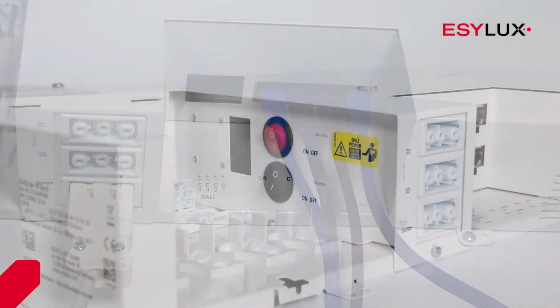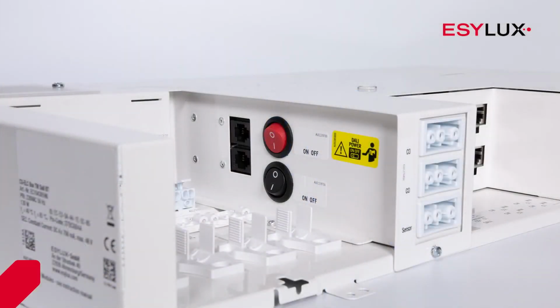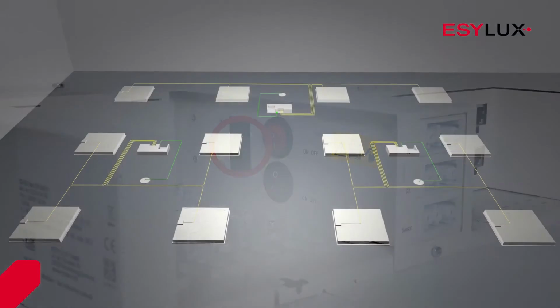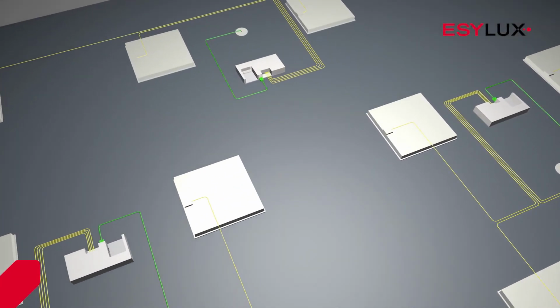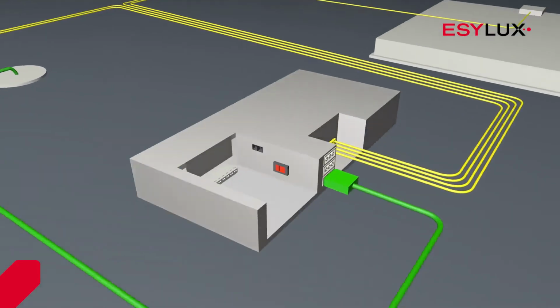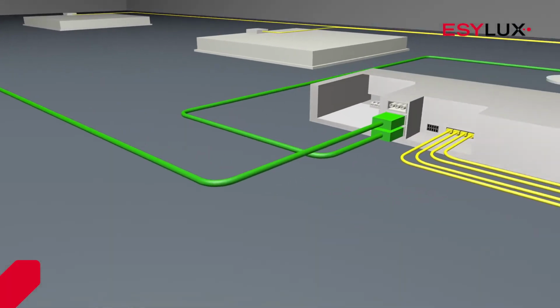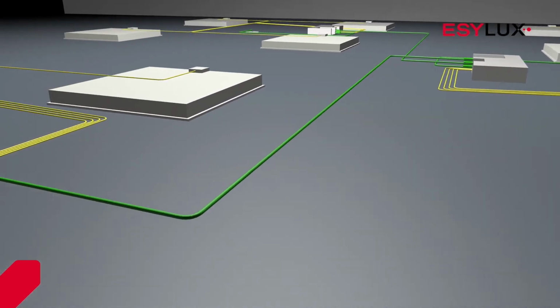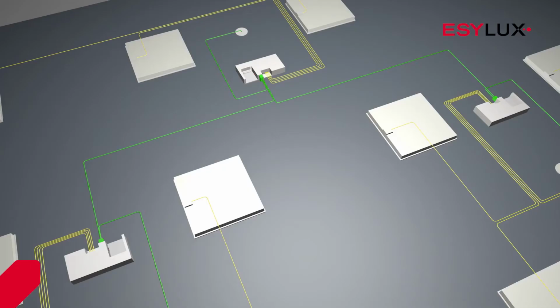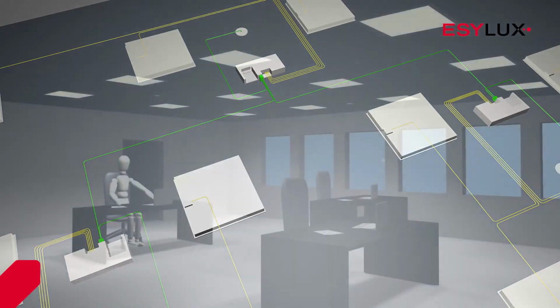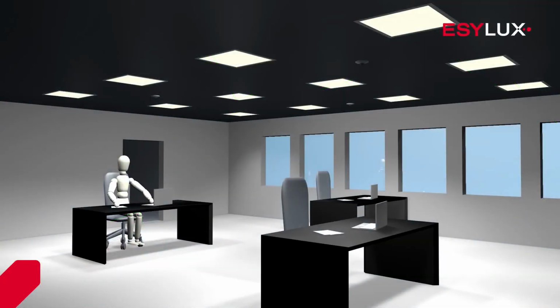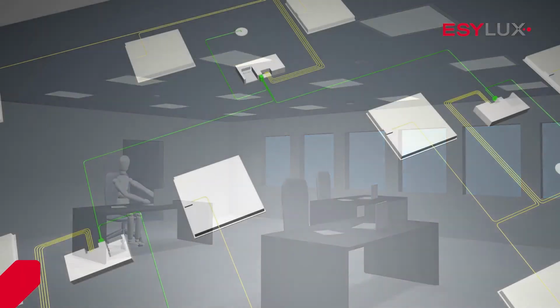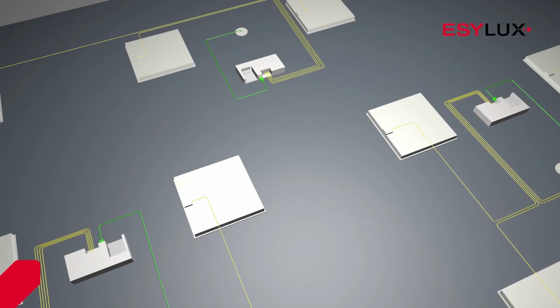If you wish to combine multiple SmartDrivers, there are two possibilities: connecting via the Dali C0 interface or via the ELC bus. If SmartDrivers are connected using Dali C0, all connected lights form a lighting group. This means that all settings, such as light target values and switch-off delay time, apply to all lights, as does all instances of a presence detector being triggered and all Dali button commands. This grouping is not ideal for some room configurations.